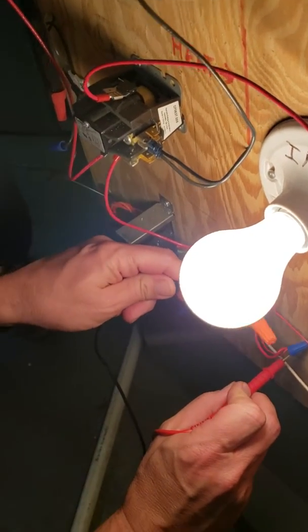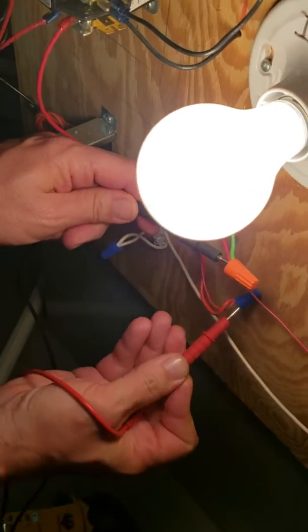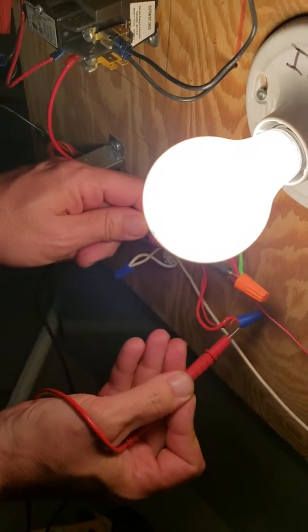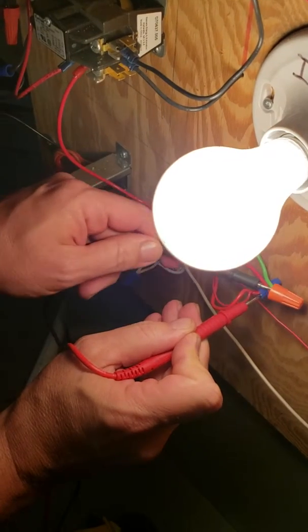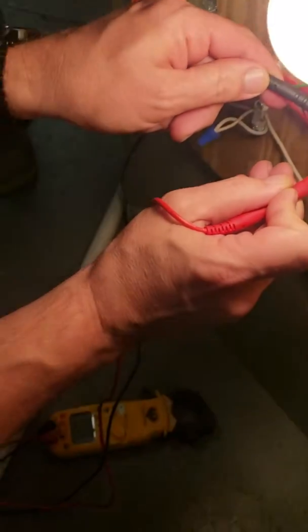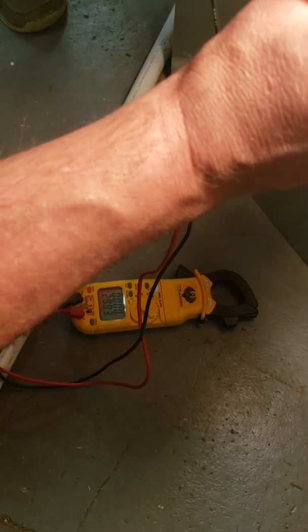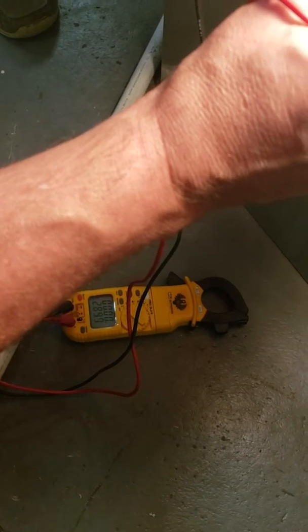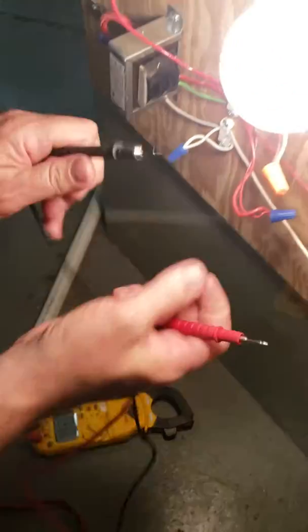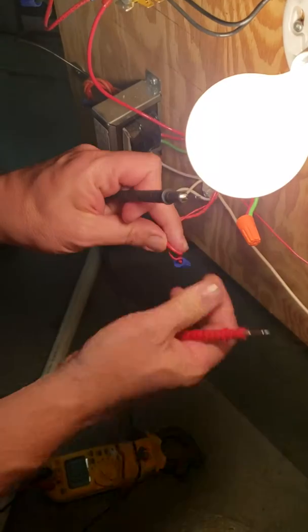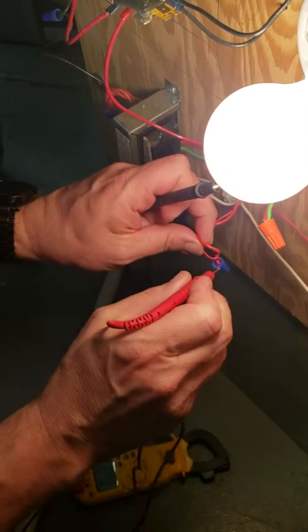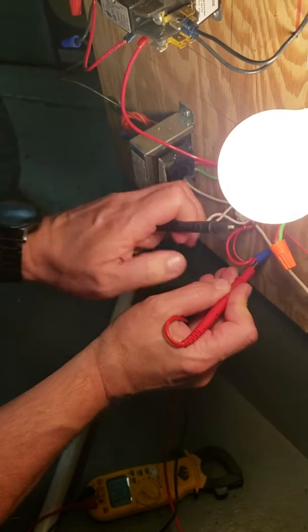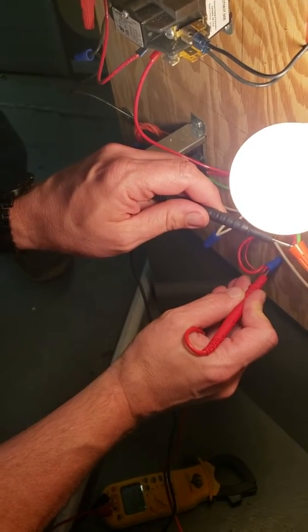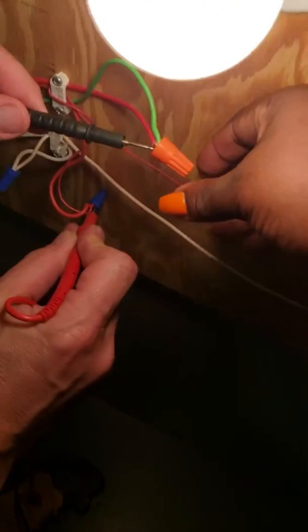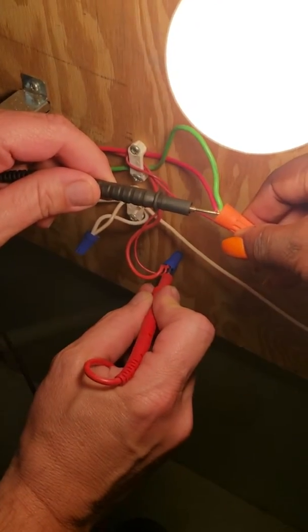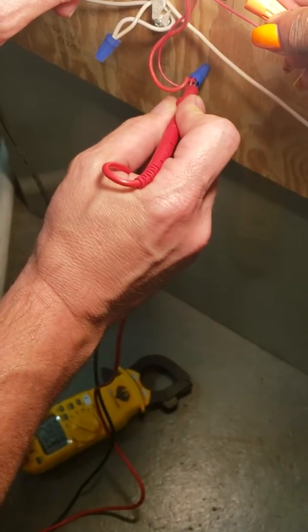Gonna go here to here. Do I have anything on my transformer? A little bit. Which one are we reading, the top one or the bottom one? Bottom. 2 point, dancing between 2.8 and 2.9. What the heck? I don't think you're getting a good connection. That wire's kind of exposed on that green one. 27.6. So I have output on my transformer, don't I?